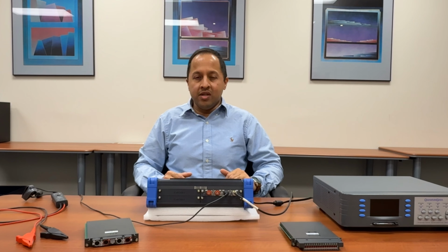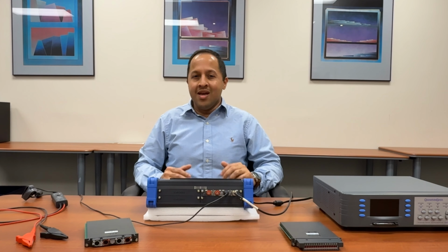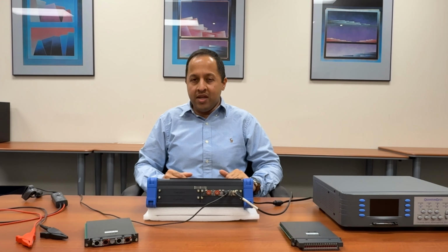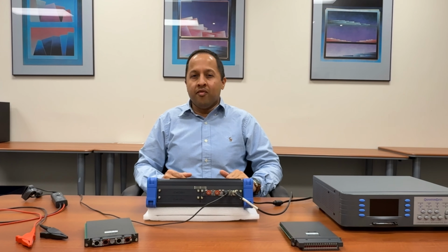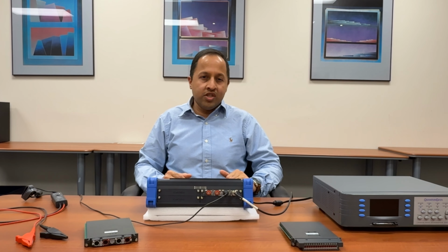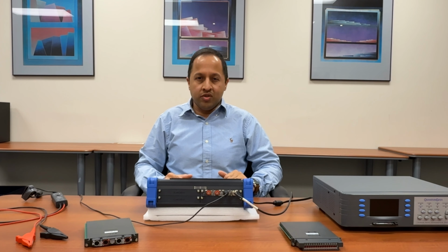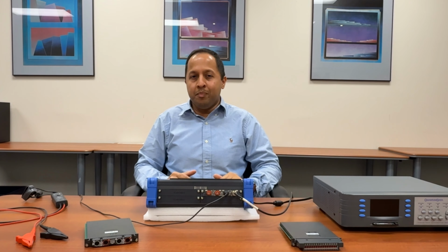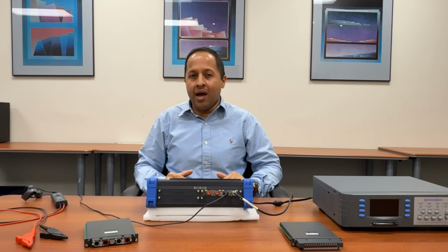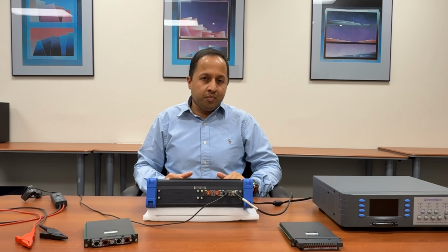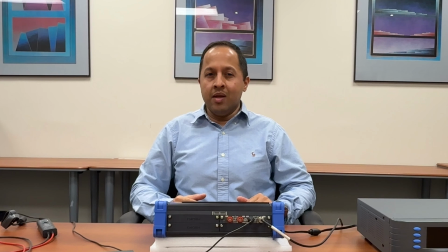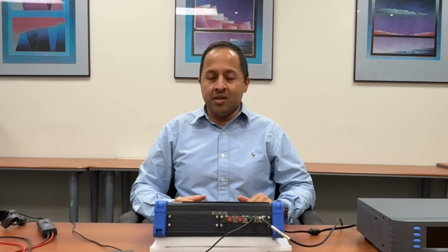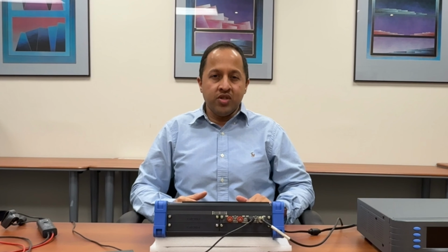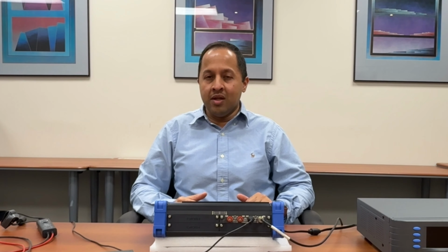Lastly, electric utilities rely on pressure transmitters to help monitor and manage critical processes from combustion and steam generation to cooling and emissions control. Pressure transmitters depend for their accuracy on being calibrated to a range that corresponds to application needs. Therefore, the MR8875 can be used for verifying response times, such as damping of pressure transmitter during calibration and monitoring signals during troubleshooting.